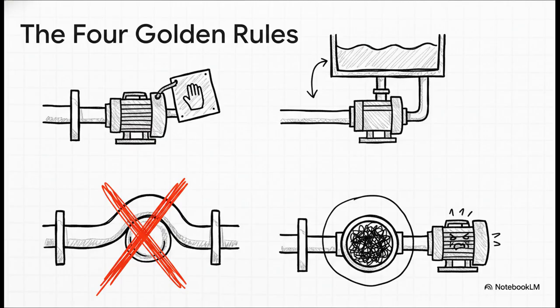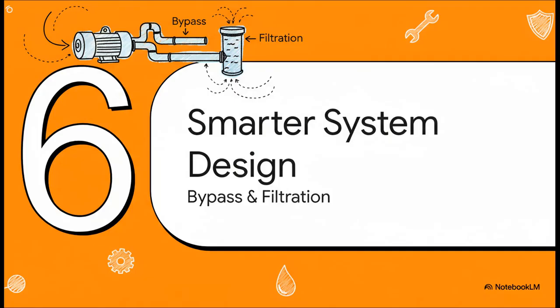Rule 1, just leave it alone. Don't put anything unnecessary in it. Rule 2, keep the pump below the water level so gravity keeps it flooded with water. Rule 3, design the pipes so air can't get trapped. And Rule 4, and this is a big one, do not put fine mesh strainers where a simple clog could starve the pump.